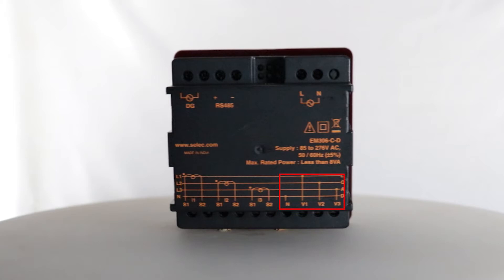Now we will connect the voltage inputs to V1, V2, V3 and neutral terminals for voltage measurement. The DG terminal is for generator input for dual source energy measurement — connect 85 to 276 volts AC. The RS485 port is for Modbus RTU communication to communicate the device over a laptop, PC, or PLC systems.